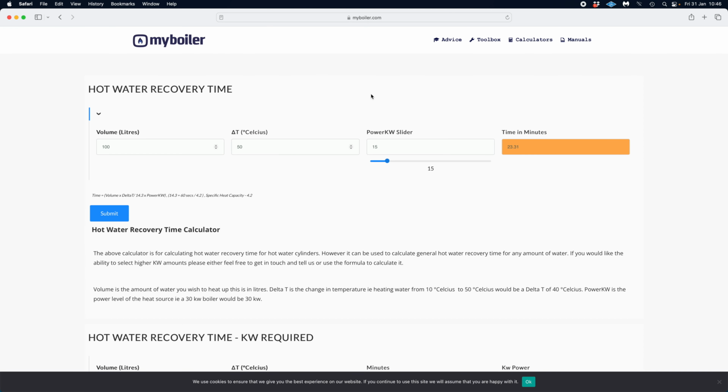So we have a couple of rule of thumb figures which we've been working on for many years now, and I can still see why we do it, but we want to question that and challenge the narrative as always. Generally, for high output heat up times, gas boilers, that sort of thing, for hot water cylinders, you would be looking at a storage capacity of about 35 litres per person per day. And if you've got slower heat up times, like heat pumps would be, because they're lower outputs of kilowatt rating, you'd be looking at a storage of around 45 litres per person per day.